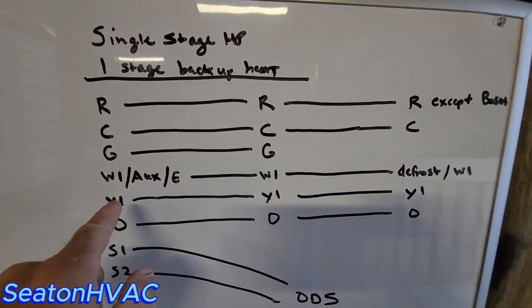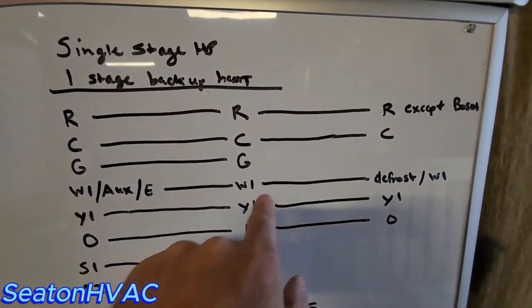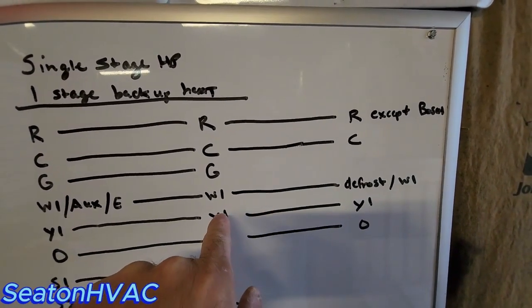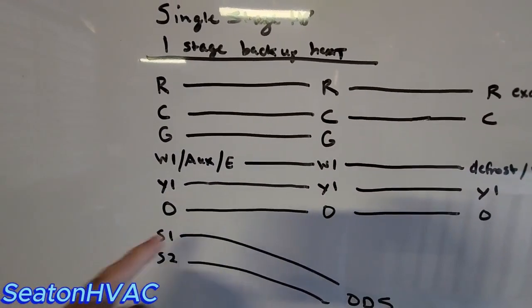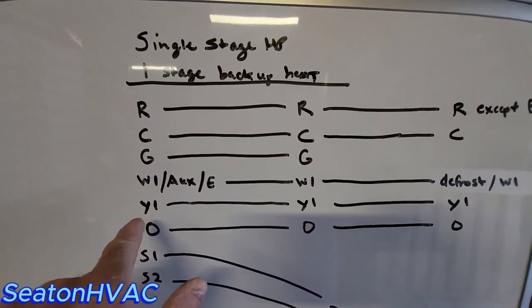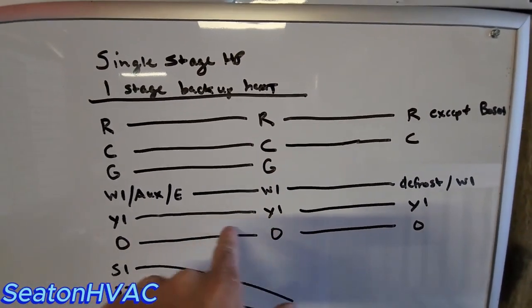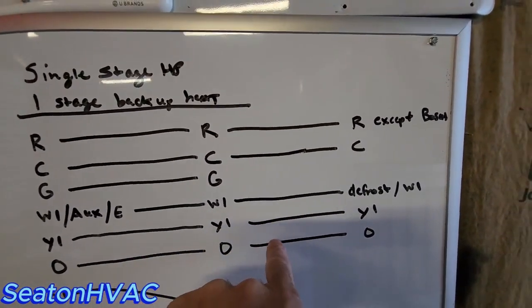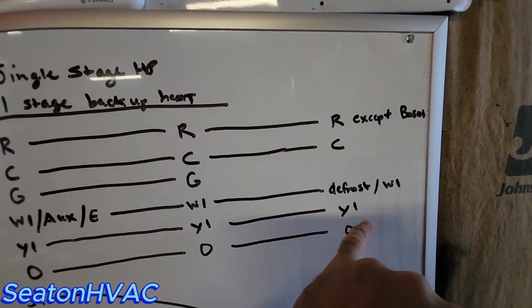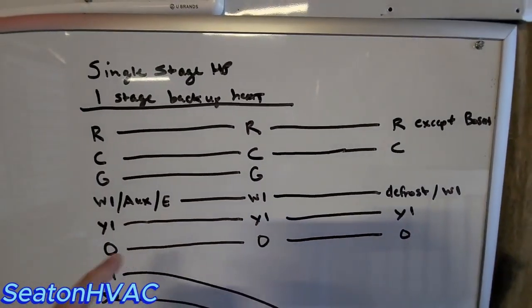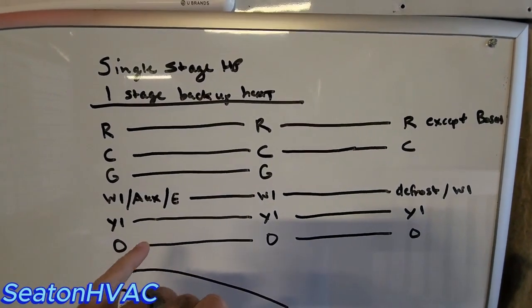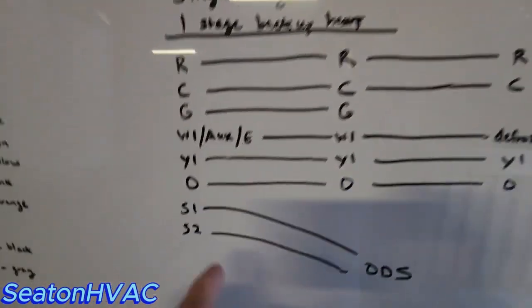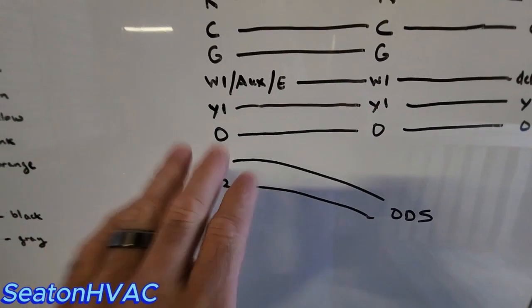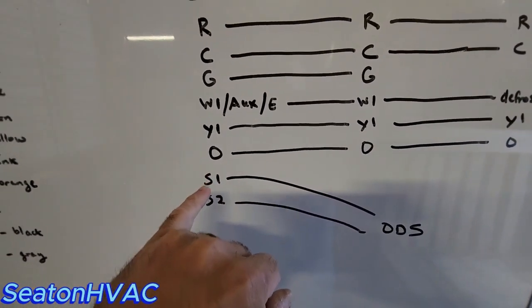Y1, same, first stage compressor, yellow, from the thermostat to the air handler, and then from your air handler to your outdoor unit, and then O, and I should put O/B here, so O/B is going to be your orange wire, O/B to O/B. Now on some of the units like the Bosch, the Rheems, you'll need to switch that in the thermostat to have it energized in heating, which would be your B. So, and then another thing that most heat pumps should have is a two-wire outdoor sensor.